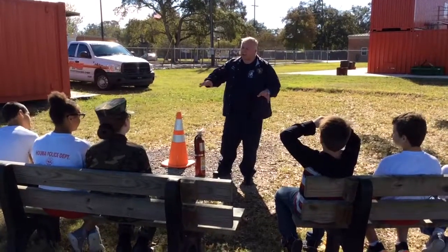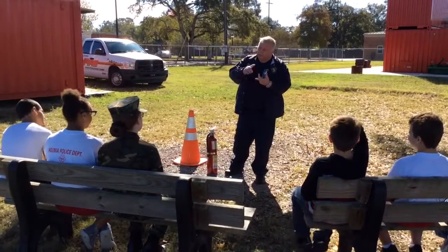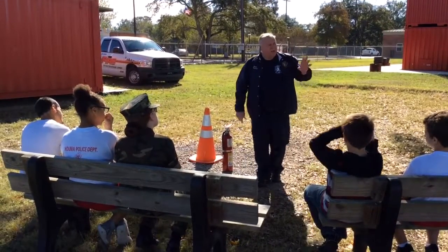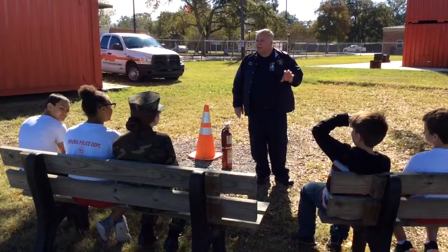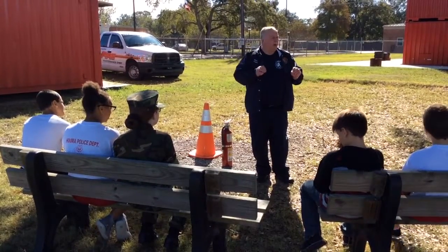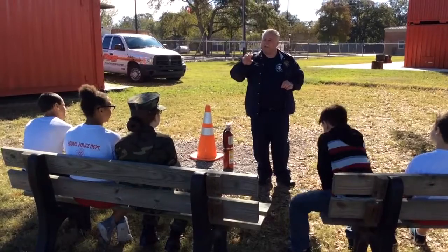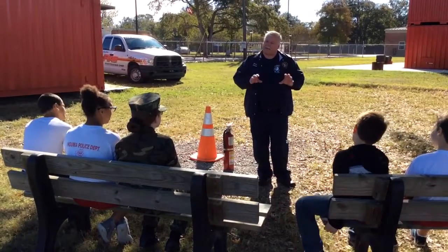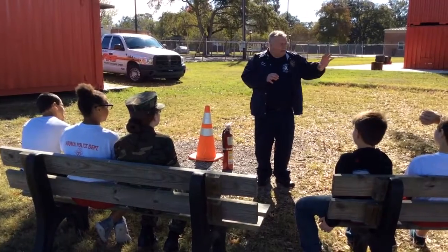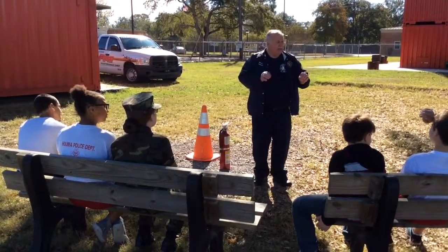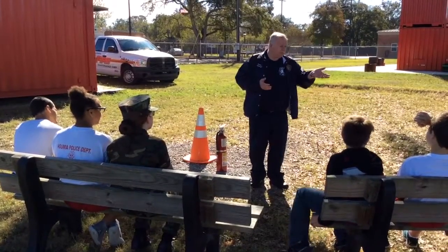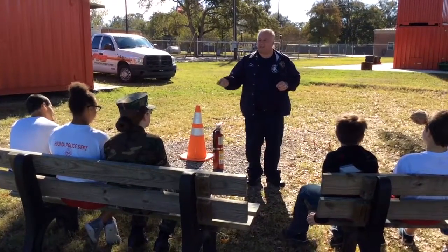Anything that leaves ashes, like wood or paper products, is a Class A fire. Okay. There's a Class B fire, which is another way to remember is boiling liquids. B, boiling liquids. A Class B fire is going to be flammable liquids, flammable gases. Okay, Class B. So gasoline, diesel fuel, that is a Class B fire.